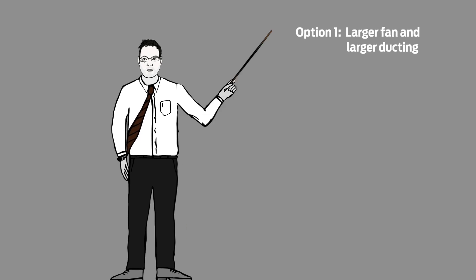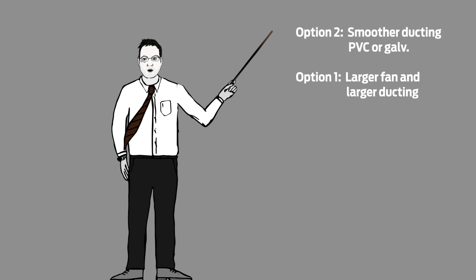We can go up a fan size if the 8 metre run is fixed, which will mean larger ducting. A simpler option that might not need any additional rework to provide enough room is to go to smoother ducting, for example PVC or galv.